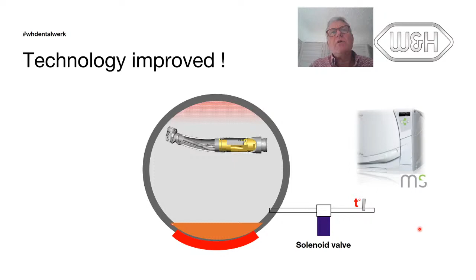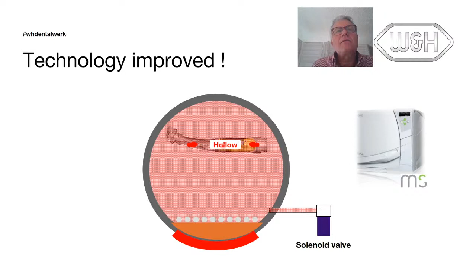This is how our MS, we have two machines, MS, let's say we call MS dental and Lina, let's say surgical. This is how it works. The machine will pre-vac the chamber with this air removal system. The only thing is that some hollow instruments may retain some air pockets. So when we talk about surgical units, surgical instruments, maybe you switch to Lina. Lina offers what we call a B-type cycle.